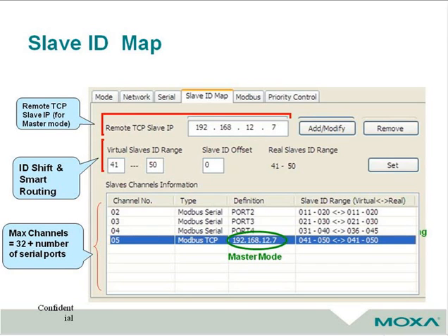Moving on to how slave IDs are mapped on the MGate MB3000 series. When a Modbus master requests information from a Modbus slave, the request is addressed to the desired slave's ID, which must be unique on the network. If this is not properly addressed, a request sent to that slave ID will receive more than one response, causing communication error.